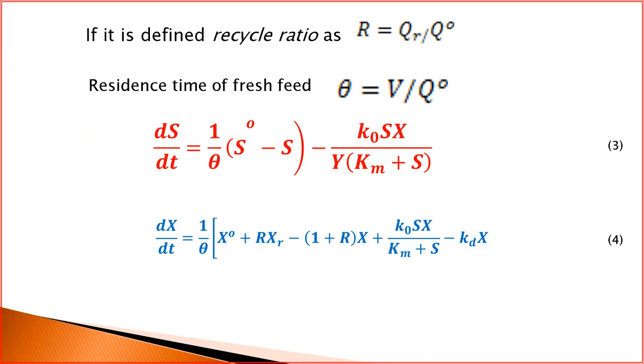If the recycle ratio r = Qr/Q0 and the residence time theta = V/Q0 are defined, the simplified balance equations become: dS/dt = (1/theta)·(S0 − S) − k0·S·X / (Y·(Km + S)); and dX/dt = (1/theta)·(X0 + r·Xr − (1 + r)·X) + k0·S·X / (Km + S) − kd·X.